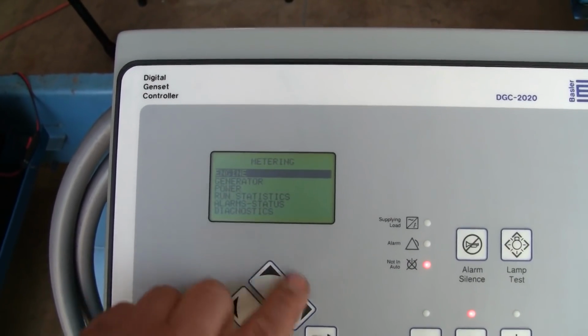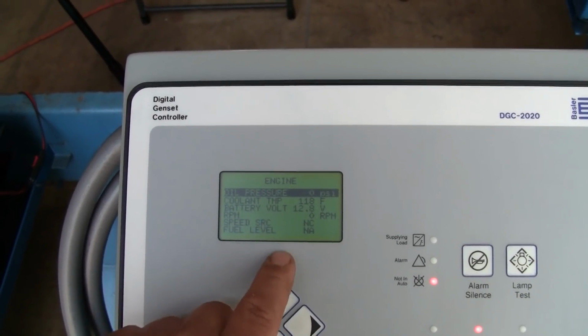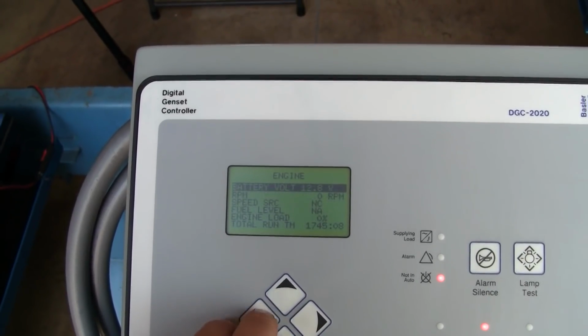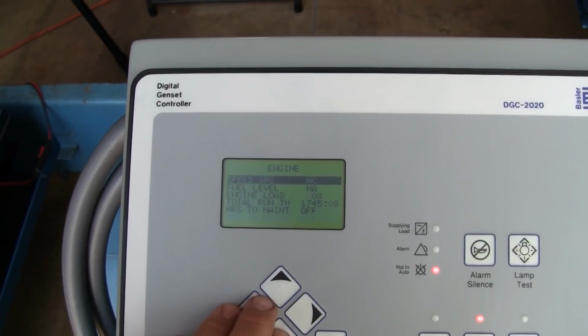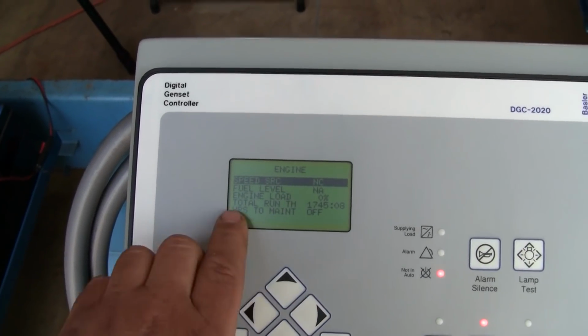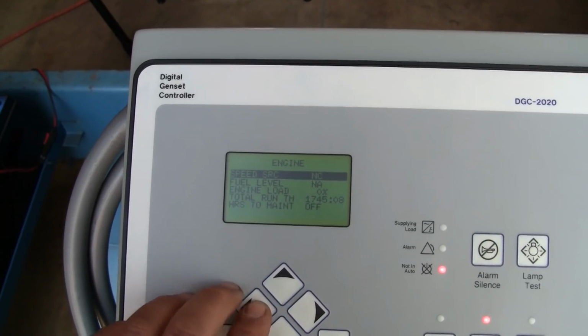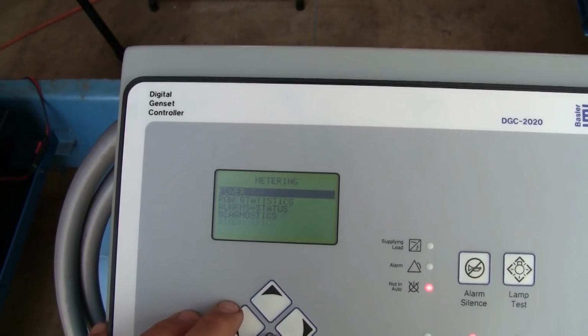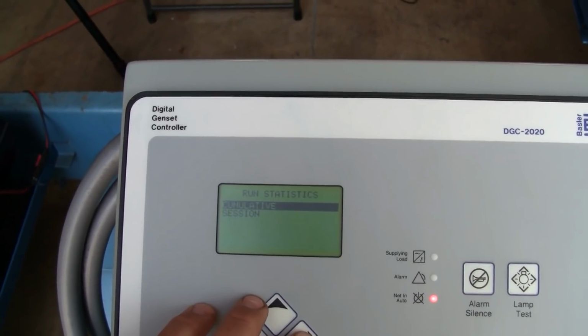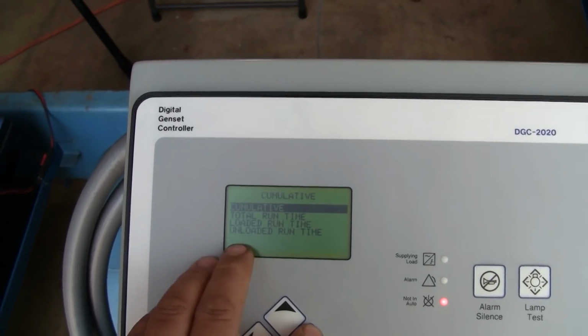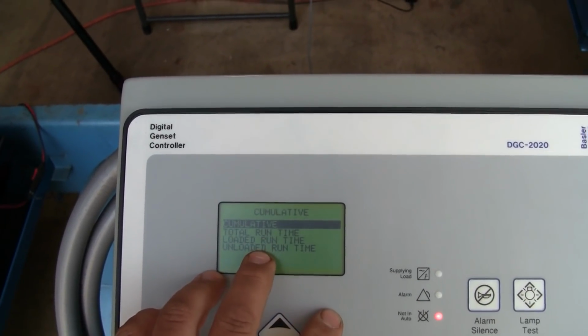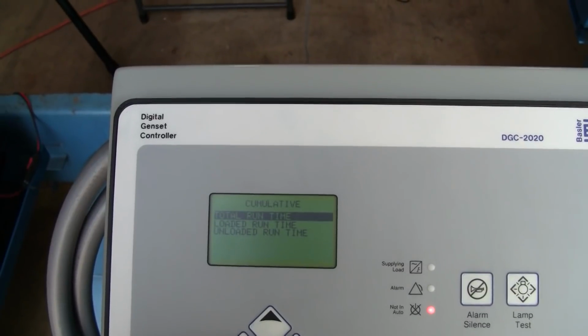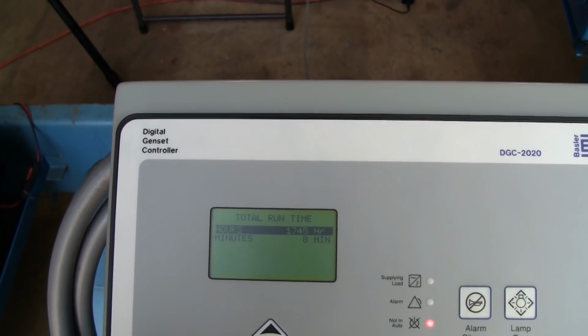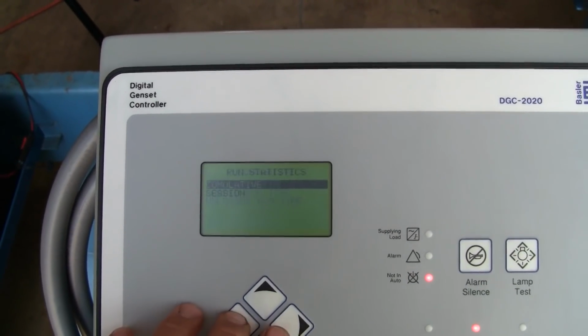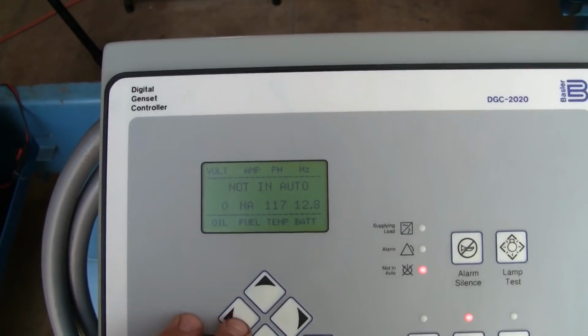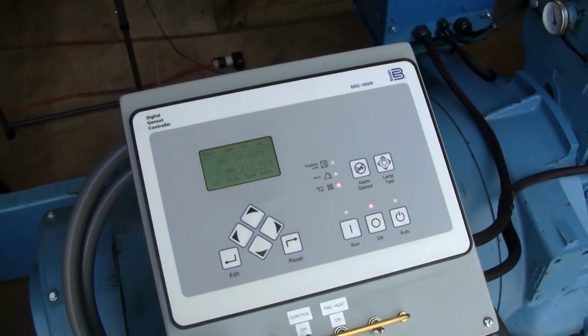The metering, we got engine metering, oil pressure, engine load 0%. You can set maintenance timers. There's our total runtime. I usually get that from run statistics, cumulative, and you can see the total runtime loaded or unloaded. I usually just look at total. 1745 hours and 8 minutes. All right, well, let's go take a look at the software.